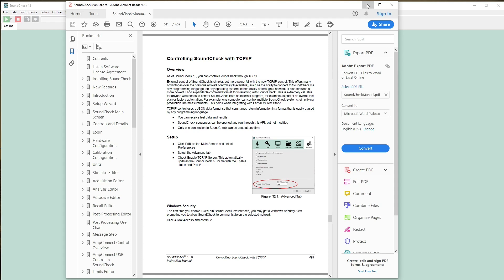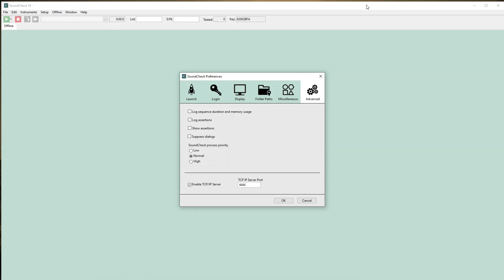For example, you can store parameters like limits, test level, and test signal externally, so a single sequence can be used for multiple products. This simplifies your sequence and the number of sequences to maintain, particularly useful on the production line.